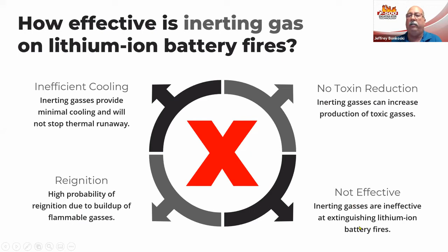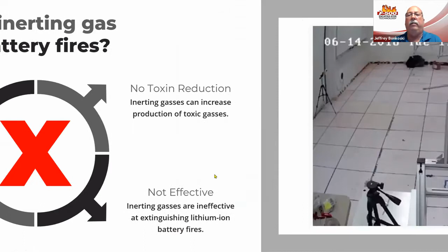It did nothing to remove the flammable nature of the gases. So when they opened the door to gain access, they had an explosion causing injury to the firefighters. Things we need to consider when we look at the design of these systems. There's minimal cooling, and it doesn't stop thermal runaway, reignition, or those toxic gases. It's doing nothing to help eliminate or reduce those toxic gases. So there's very little effect that inerting gases will have on your lithium ion batteries.